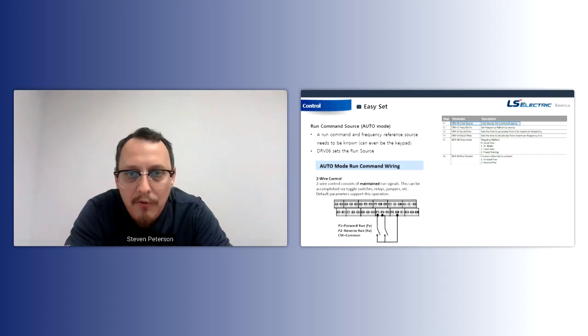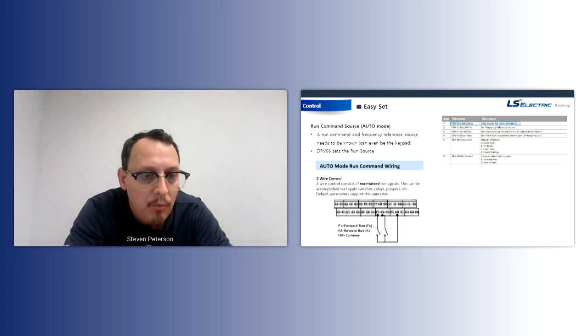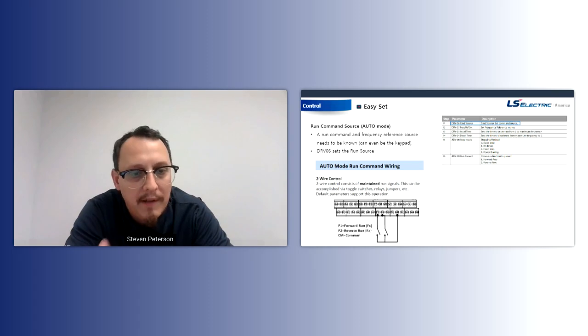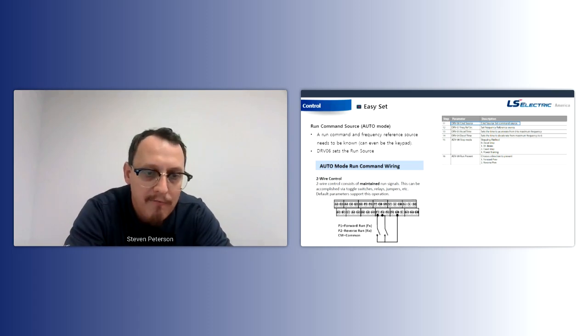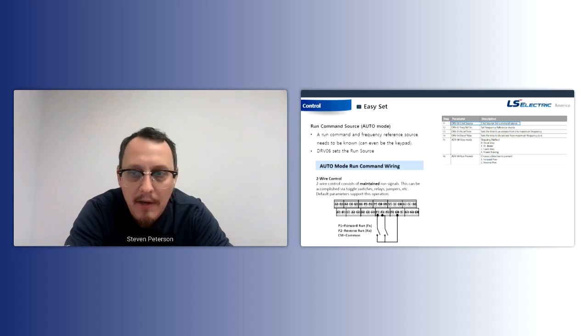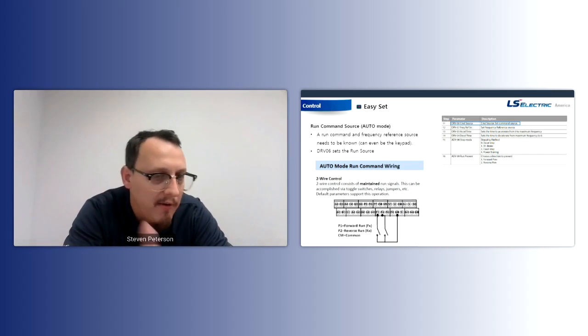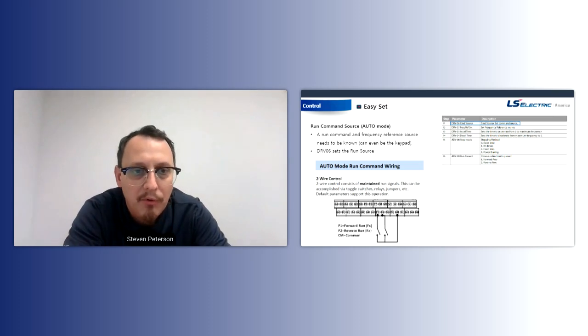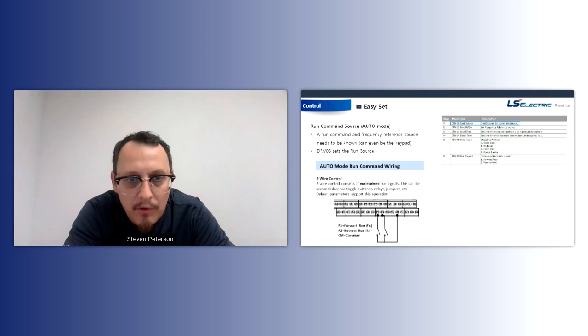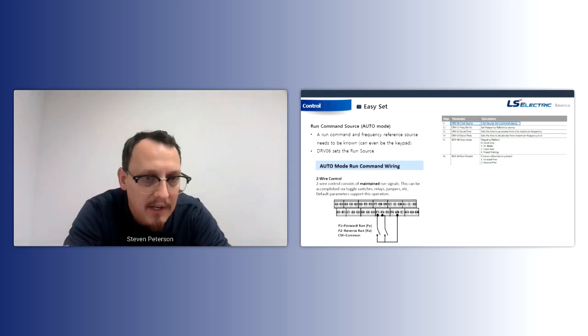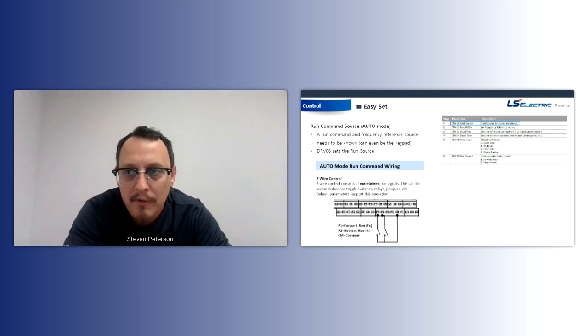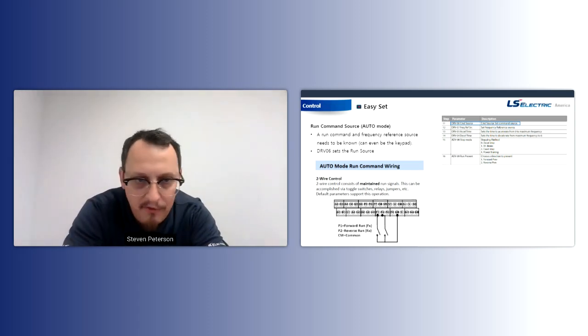So it's going to say, where's your command source? And most of the time, and most of the calls we get, people are running P1 or P2 to run their drive. So those are terminals, and we call that FX for forward and then RX for reverse. Most pumps are just running forward. So all you really need for wiring is a contact closure, like a dry contact for P1 to CM. When you close that contact, the drive runs in auto, forward direction. Okay, so that's what this parameter is asking. You could set it to run off of the keypad. You could run it off of communications. There's a few different options, but most people just have a run relay that triggers the drive to start. So that's what this parameter is.